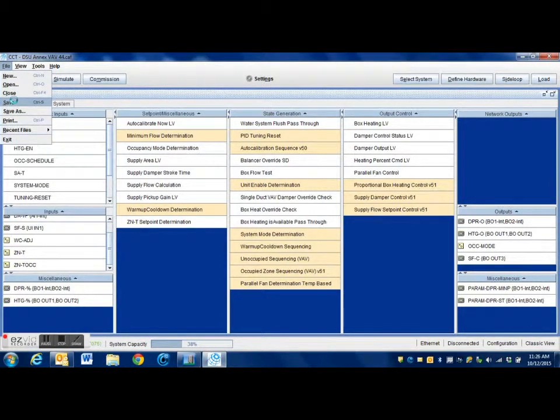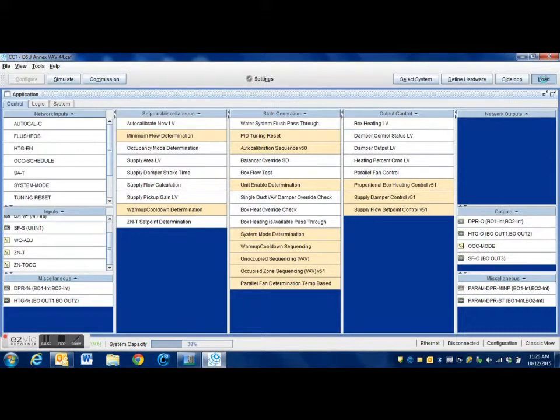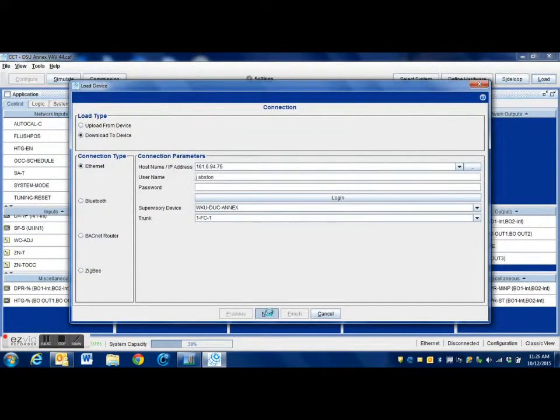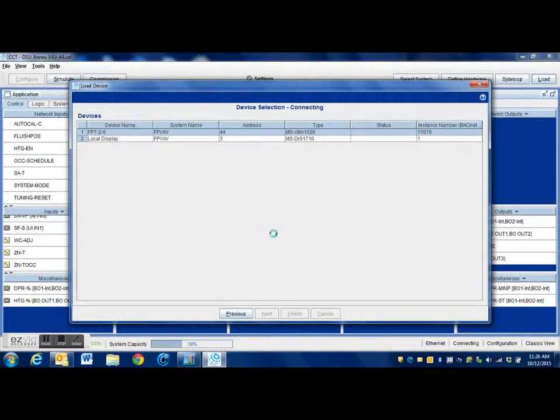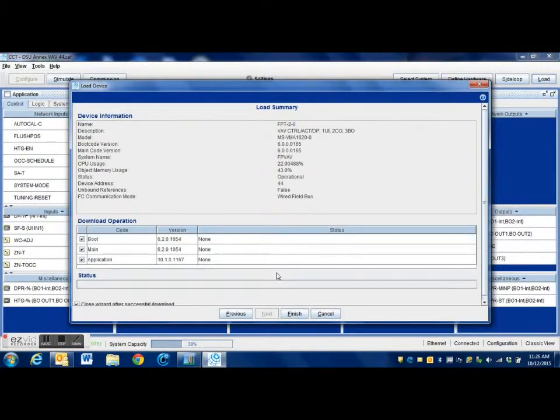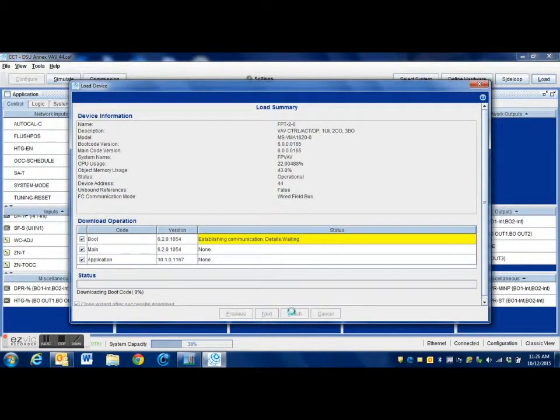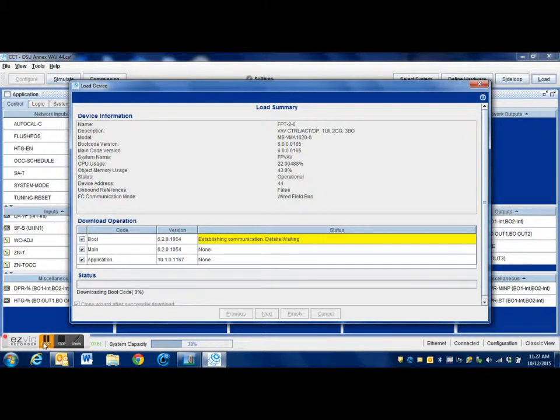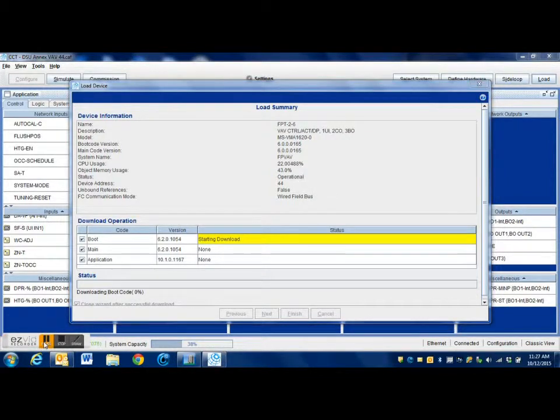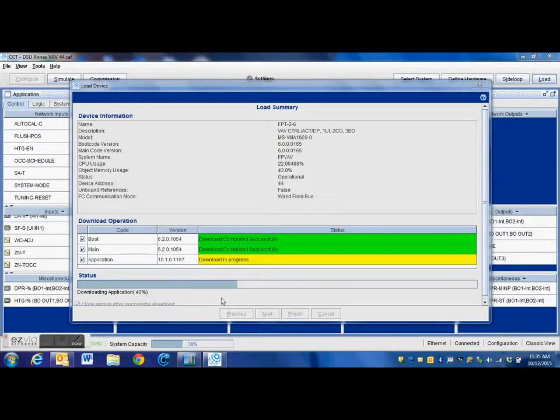Now that we have the program saved, I'm going to load this back into that VAV. The unique thing about the CCT programs is it will only let me load the program into the box that it is programmed for, based upon that address. Since this is a newer version of CCT, I've got to load the boot section. I've got to basically upgrade the controller, so it's going to take a bit of time. I'm going to pause this video and we will come right back.